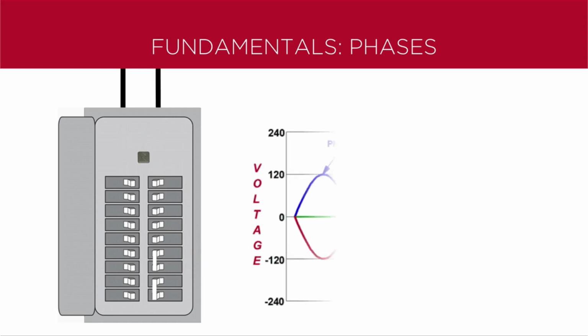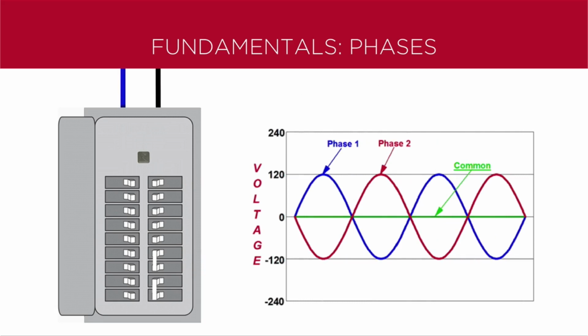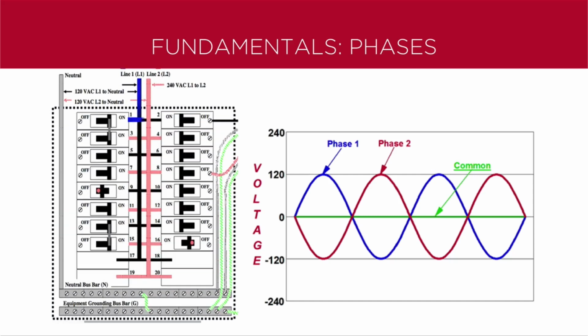The 2 service lines coming into the fuse box run on different phases. The sine waves for those phases are opposite each other, heading in opposite directions at the zero cross. Service line 1 goes to every other circuit breaker in the fuse box. Service line 2, shown in red, is on the other phase and goes to the remaining circuit breakers. As you can see, Phase 1 and Phase 2 are staggered between all of the circuit breakers.